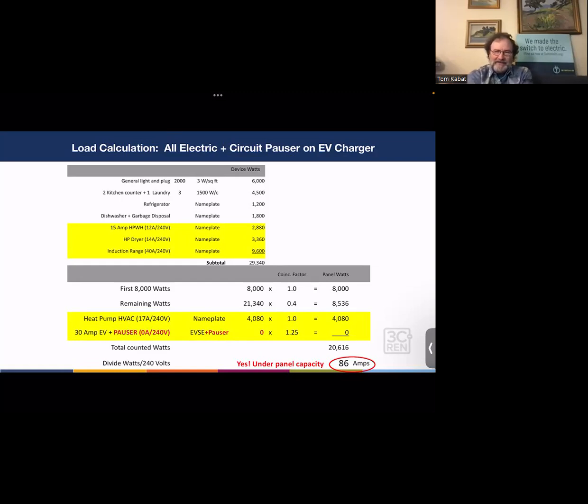And so in that case, it just drops the charger out of the calculation. The code lets you count the charger as controlled at 0 watts. And so we do the same calculation. We show 86 amps on the panel. So it did make it through there. And if we go back one slide, we can see that 100 amp panel could flow 24,000 watts. So when you look at the 27,000 watts down there, you can see that we're almost 4,000 watts over the top of that. And so we got there by controlling the EV charger.